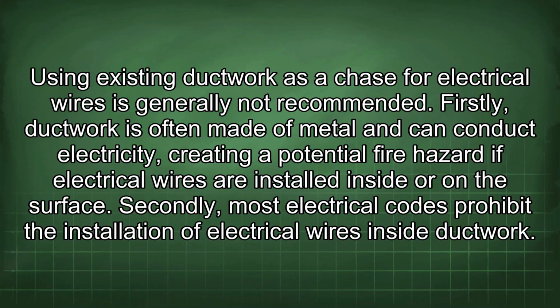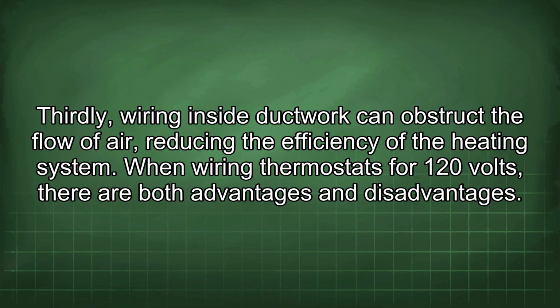Using existing ductwork as a chase for electrical wires is generally not recommended. Firstly, ductwork is often made of metal and can conduct electricity, creating a potential fire hazard if electrical wires are installed inside or on the surface. Secondly, most electrical codes prohibit the installation of electrical wires inside ductwork. Thirdly, wiring inside ductwork can obstruct the flow of air, reducing the efficiency of the heating system.